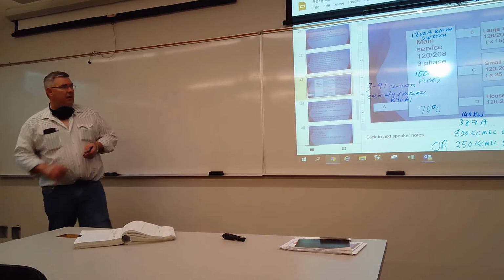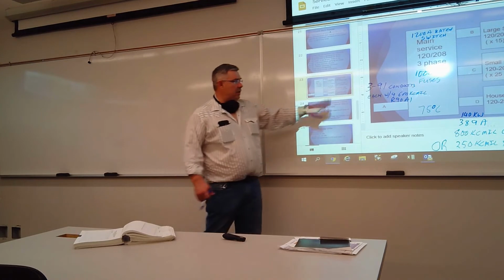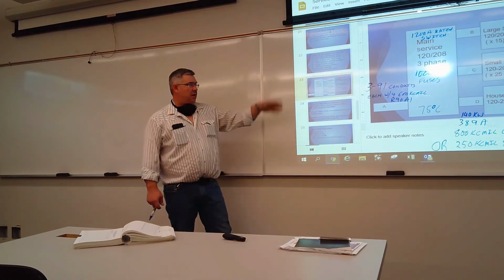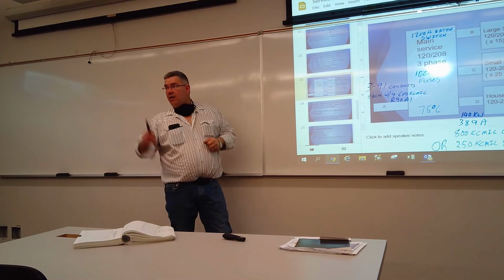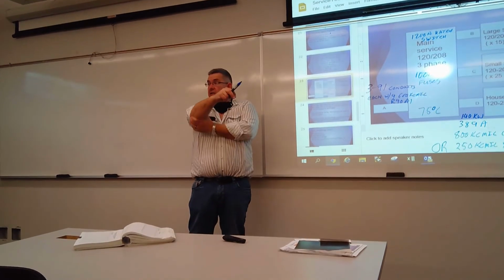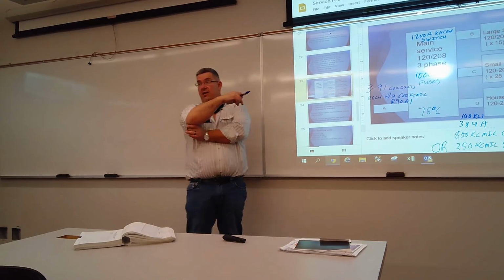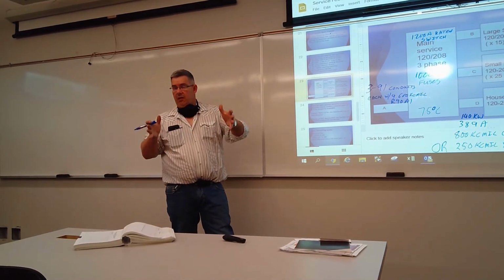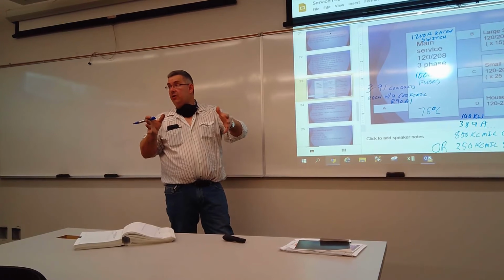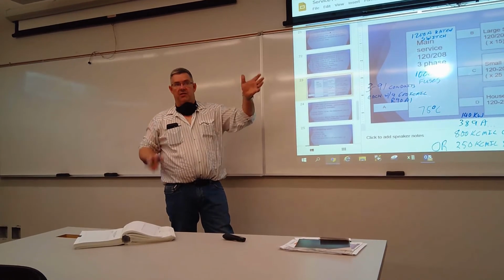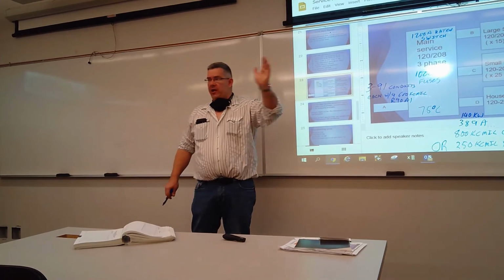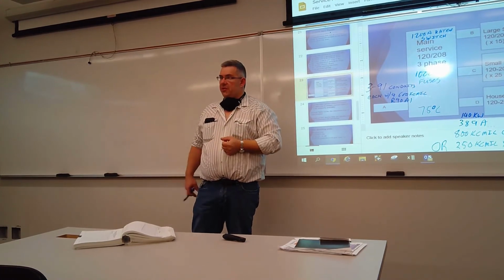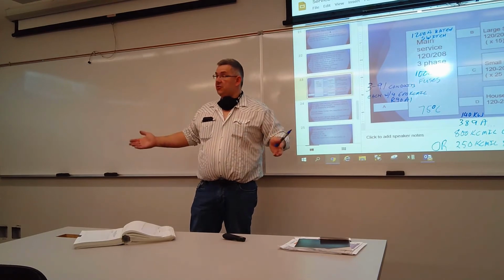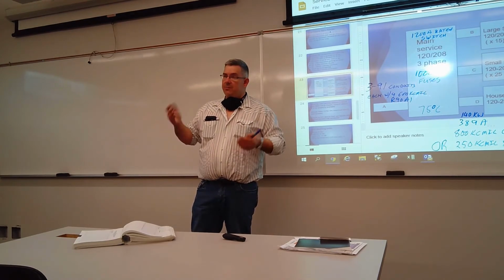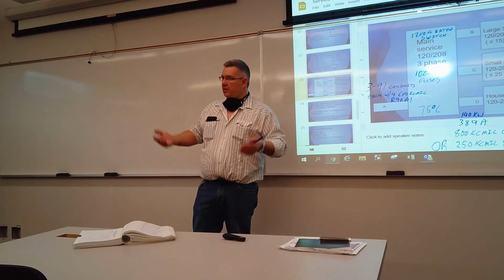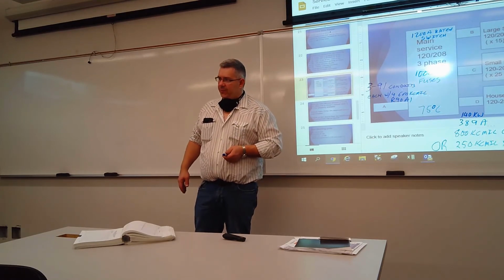It all depends. I've done fairly big installations with 208 volt services, and just did them this way. Part of the mall is a 600 volt service, and every shop has its own transformer. So there's a 600 to 208 transformer in every one of those little stores within the mall. Just because there's so much distribution: keep the voltage up, keep the current down, smaller conductors, less line loss, and on you go, right?